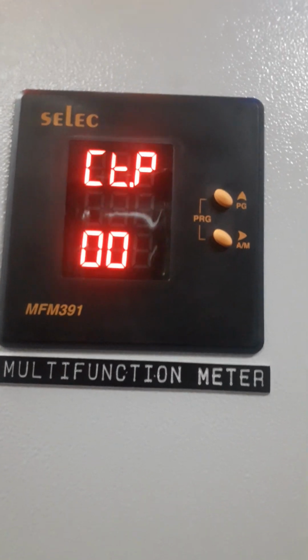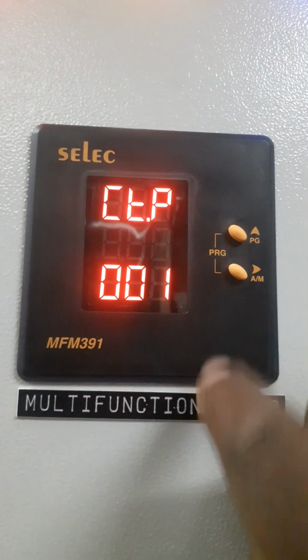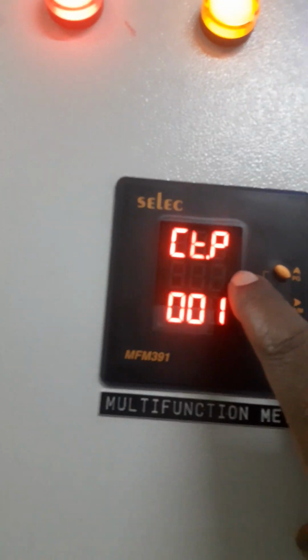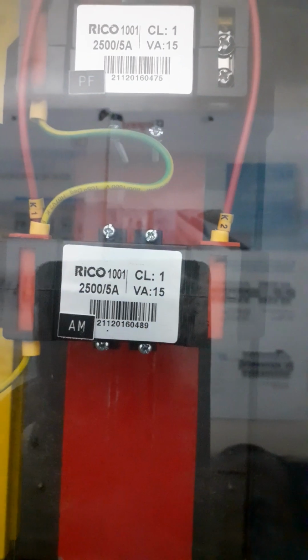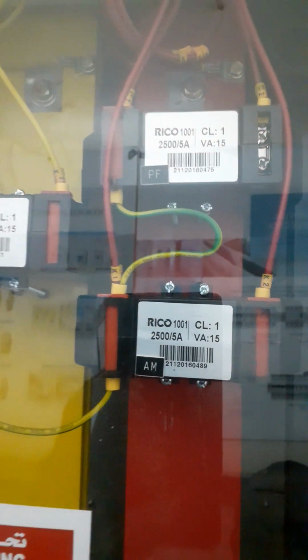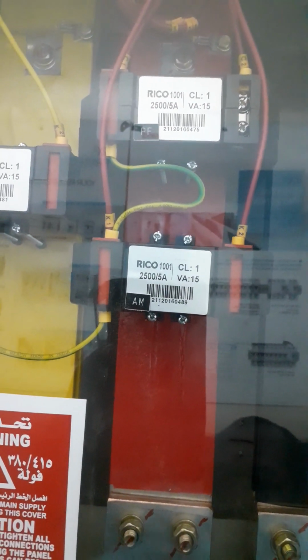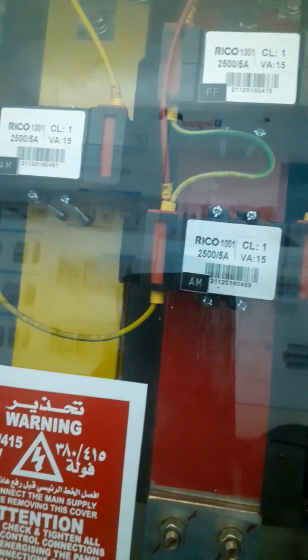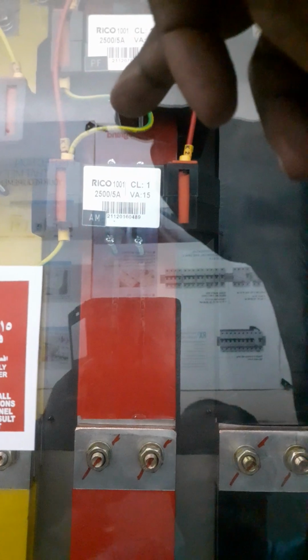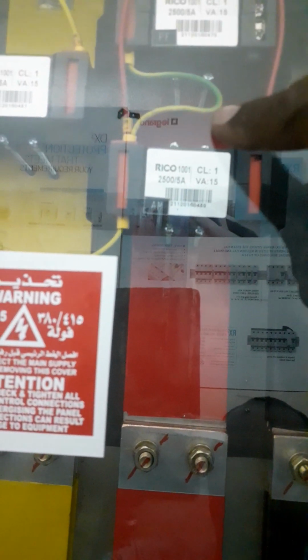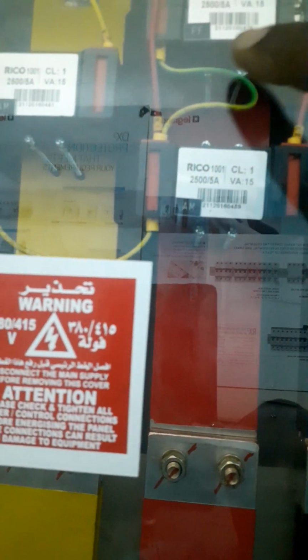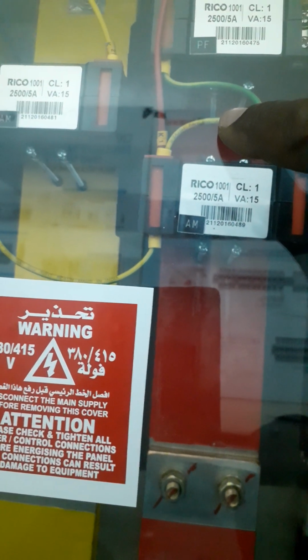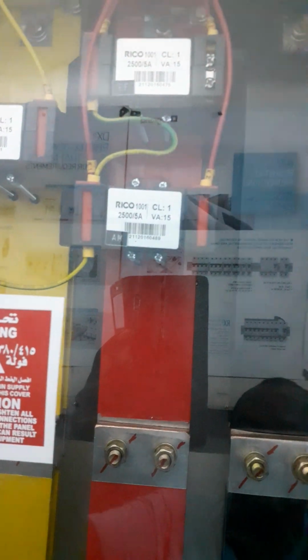Before it was indicating 0, 0. So this one I've set to 001, and the K symbol here is gone already. So how do I attain this K here? Because in our case it is 2500. The primary is 2500. The secondary side is 5 amps. The primary, that's 2500, is the actual current that flows inside the bus bar, and the 5 amps, that is the secondary side, is what we are going to read, the maximum reading. So we have to match between 2500 and 5 amps. For every 500 amps we expect 1 amp reading from the secondary side. For every 1000 amps we expect 2 amps from our secondary side.